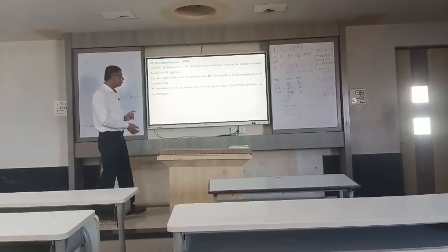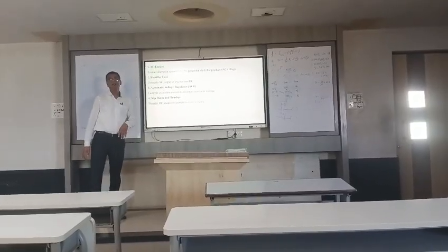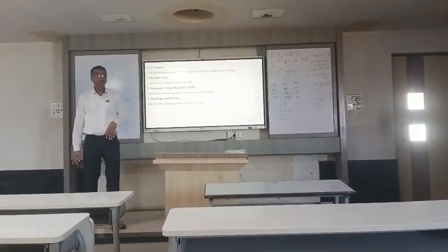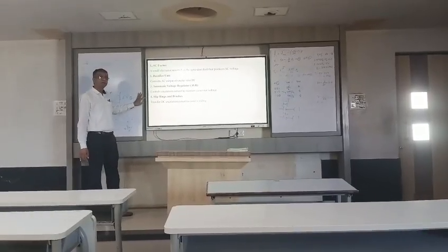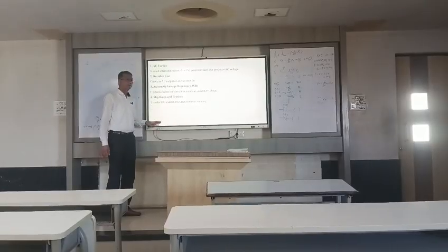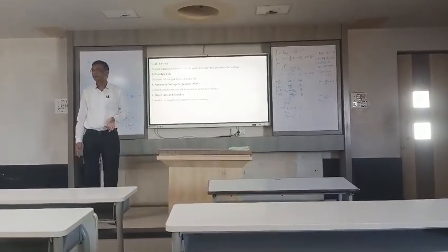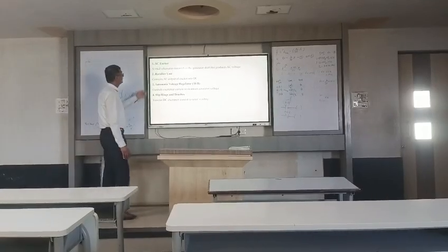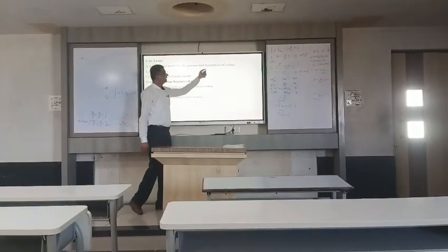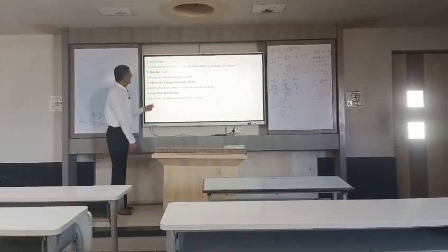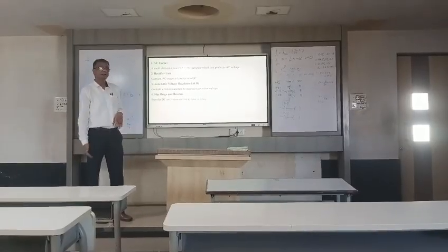Okay. Then these are the various units in the diagram you have drawn: the AC exciter, then the rectifier unit, then third the AVR, and you have the slip ring and the brushes, and each performs its function. The AC exciter is a small alternator mounted on the same shaft that produces AC voltage or AC current. The rectifier unit converts the AC into DC, provided to the rotor field winding.